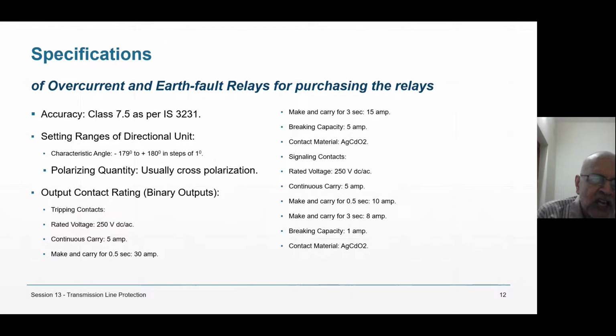Setting range of directional unit, characteristic angle -179 degrees to +180 degrees in steps of 1 degree. Very nice. Polarizing quantity. Usually we use cross polarization, that is IR and VYB, etc. Output contact rating, binary outputs. There are 16 binary outputs in the numerical relay, some of which are power outputs and some of which are signal outputs. Signal outputs, the rating will be less. Tripping contacts: rated voltage 250 volt, continuous carry 5 ampere, make and carry for 3 seconds, breaking capacity, contact material AgCdO2. Signaling contacts. That was for power contacts, tripping contacts. This is signaling contacts. Everything is given for the contacts.